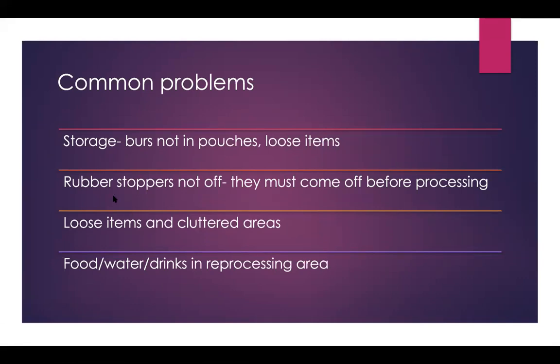One common finding was rubber stoppers left on endo files. The files for endo — the rubber stoppers have to come off before processing. Because if they don't come off, the area beneath that rubber stopper is not sterile. So you're using an endo item on a patient that is technically not sterilized, and that's unacceptable.